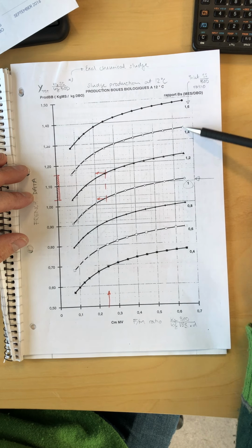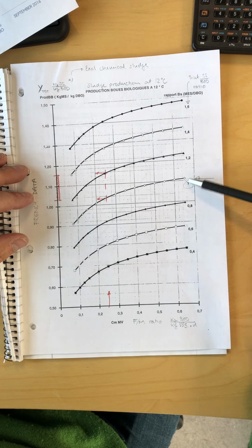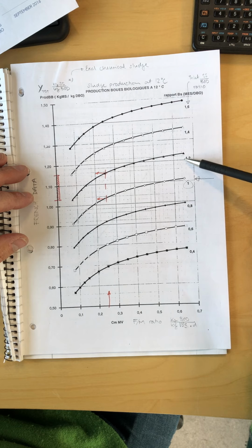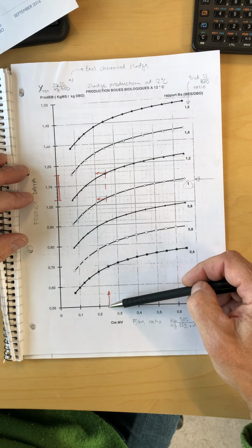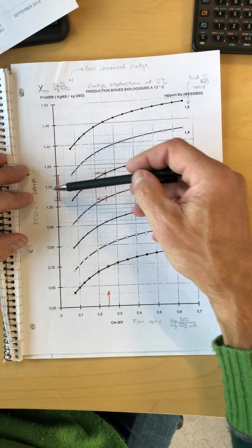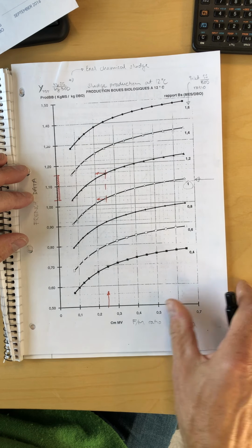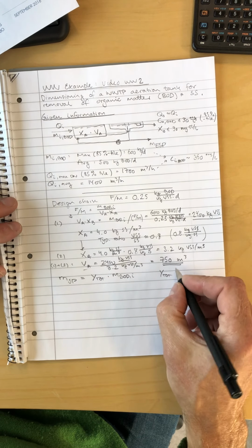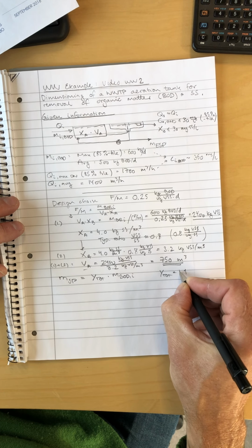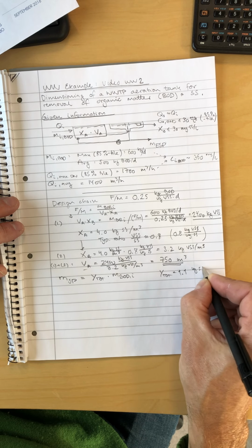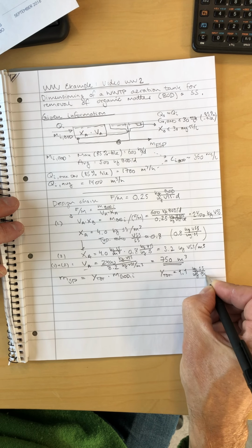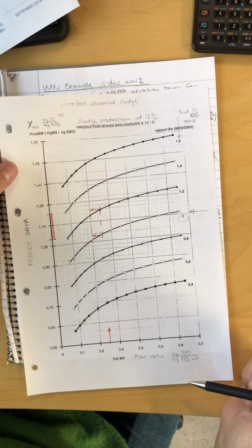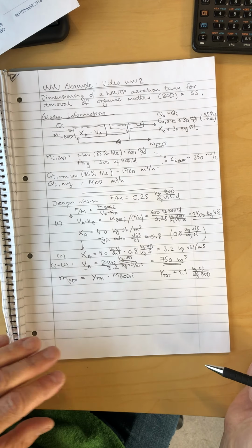I've got the ratio between suspended solids and BOD in the inlet. I haven't looked into that, but the normal range here is between 1 and 1.2. So I'm around here, my 0.25, so I get a yield constant around 1.1 kilogram of SS per kilogram of BOD. So that's what I'll assume: 1.1 kilogram sludge produced per kilogram BOD at the inlet as food, the inlet load compared to the inlet load.